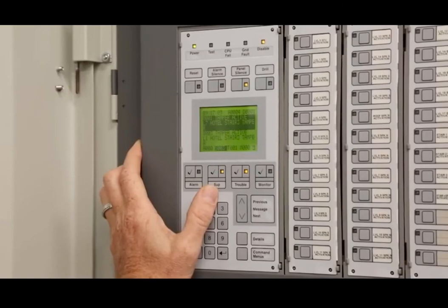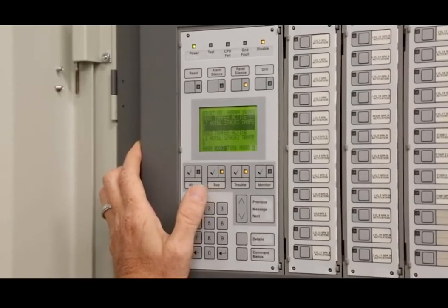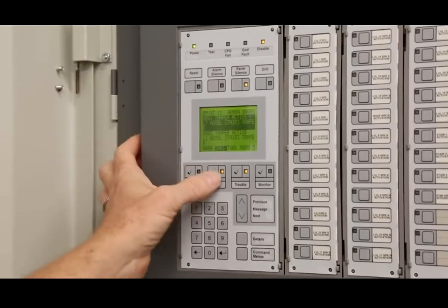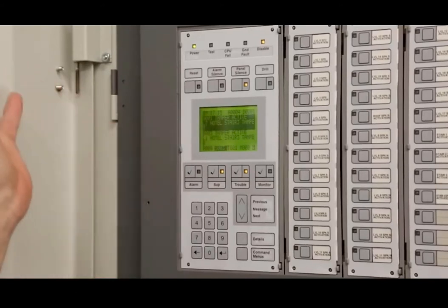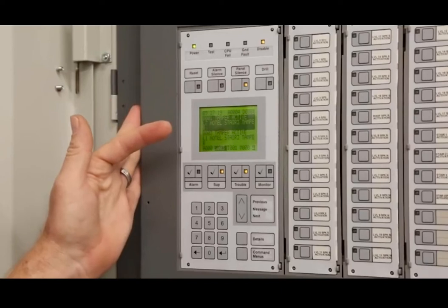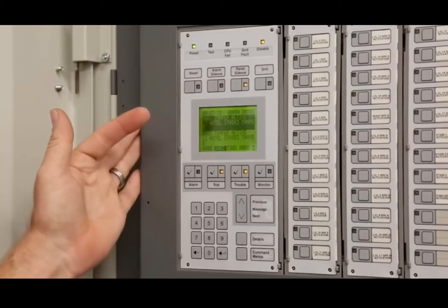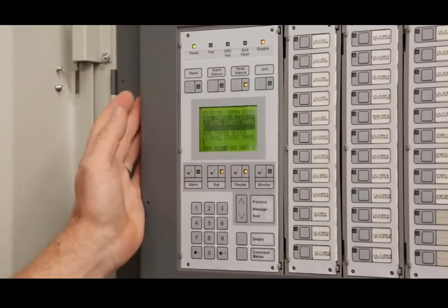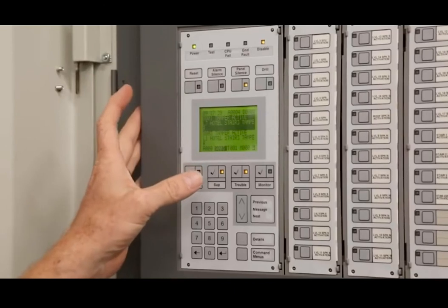All your room detector smokes are independent. They are 120 volt, but they are monitored by here. So if the supervisory goes off in room 606, it will actually tell you right here. It is self-restoring. If it is a smoke going in it, it'll probably ring off for about a minute, and that's only in that room, and you can see it right here. Okay.